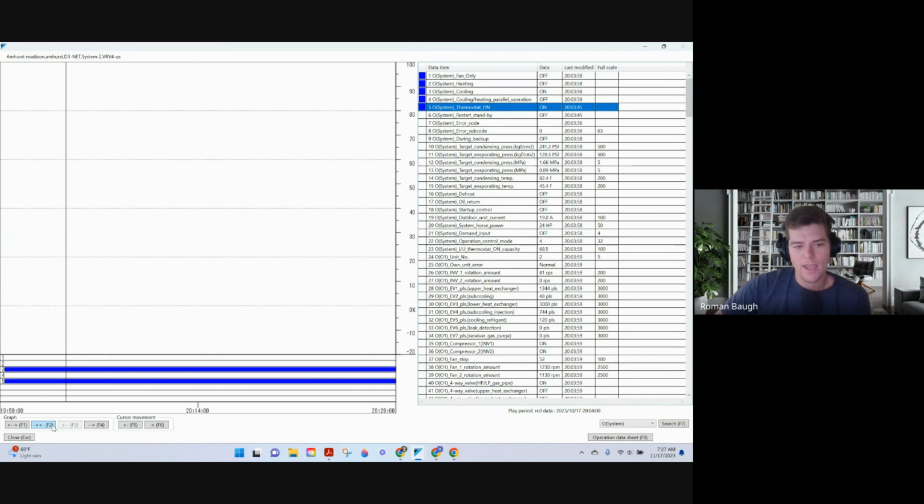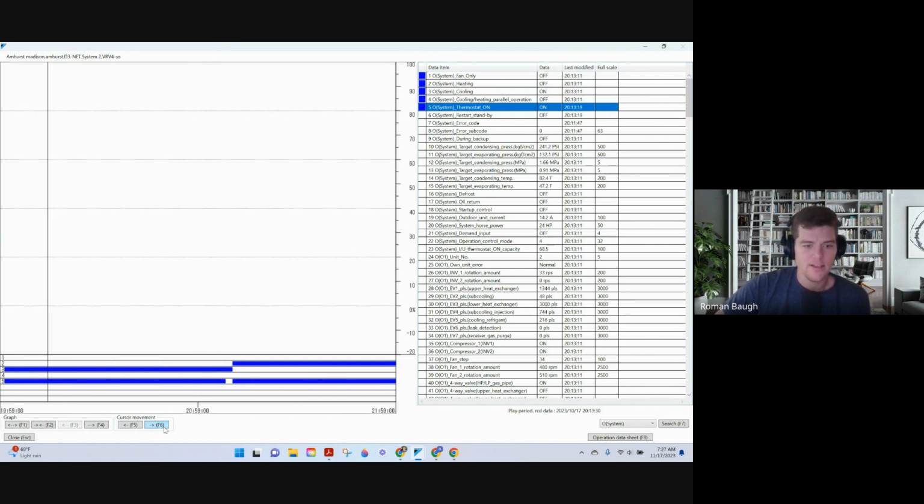Well, what if there is a way that I could show you to determine exactly what that unit is doing? Now you'll notice here at the bottom, we have some line changes. If I go over here to this data set and move through my points, you'll find that when I get all the way over here, a million clicks away, we have a change in mode operation. Line item 2 we know is heating. Line item 3 we know is cooling. Now, this is what everybody is used to doing.